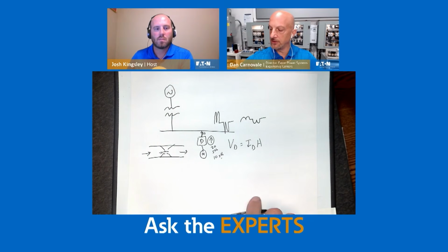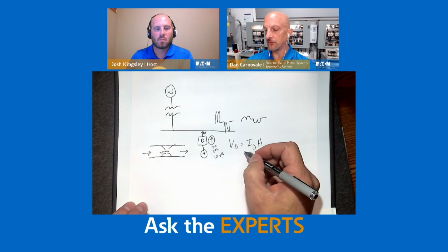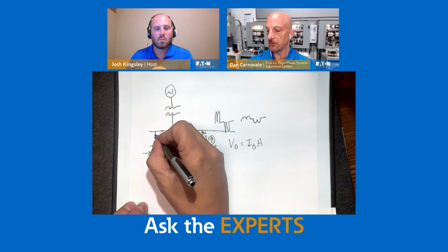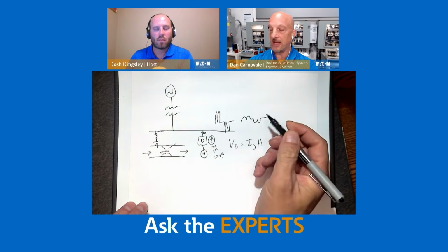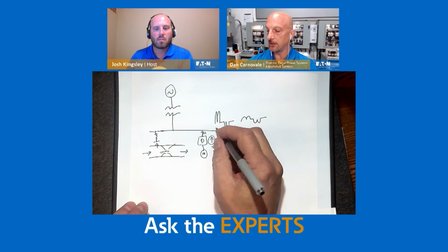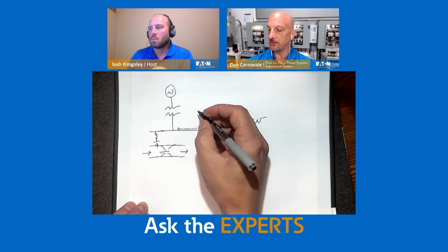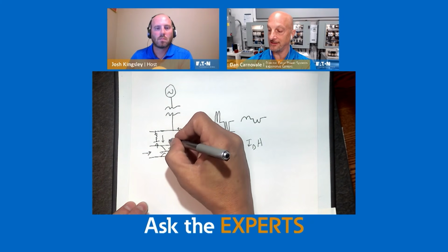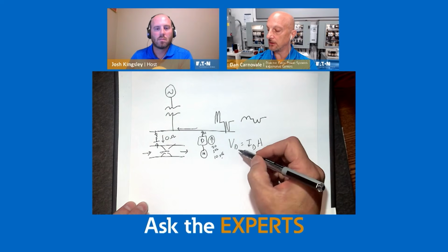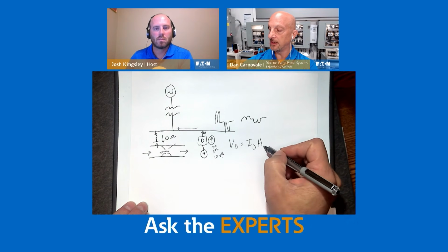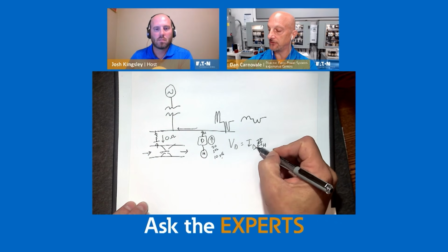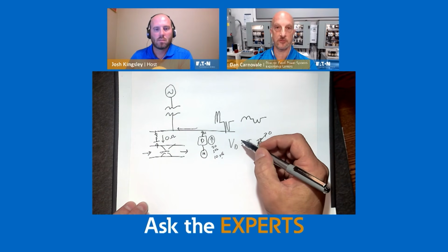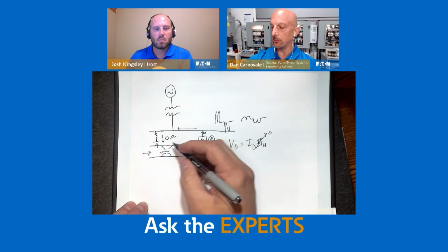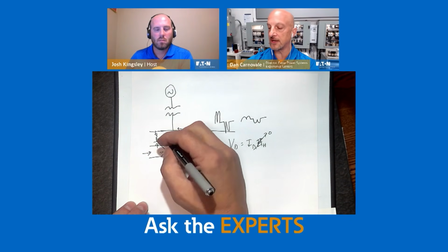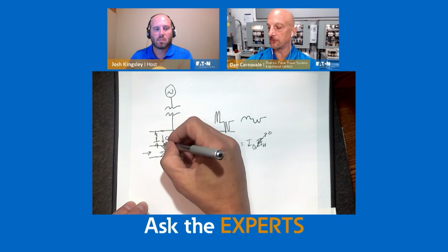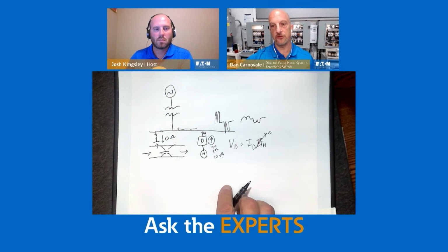As you look at other things, we talked about if we try to take the current and make it go somewhere else, we could actually put a filter over here. A filter looks like a reactor and a capacitor in series. And at a particular frequency, let's say this fifth harmonic current, when this current gets to this point, current wants to divide and go according to impedance. So if this was ideally 0 ohms, guess what? Even if it's 100 amps times harmonic impedance, if this is 0 ohms, then our voltage distortion goes back to 0. In reality, it's not going to be 0, but this is how harmonic currents flow through the system. And most times when you make a filter like this, half of the current or so goes this way, half goes this way. So those are two things that you could do.